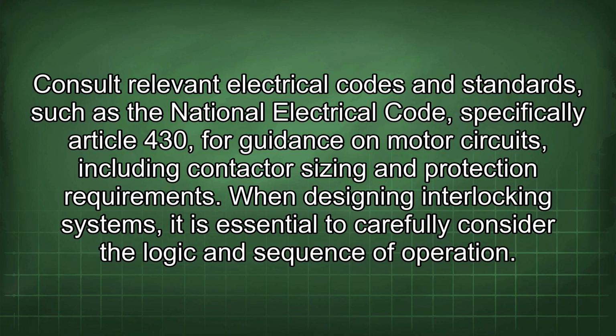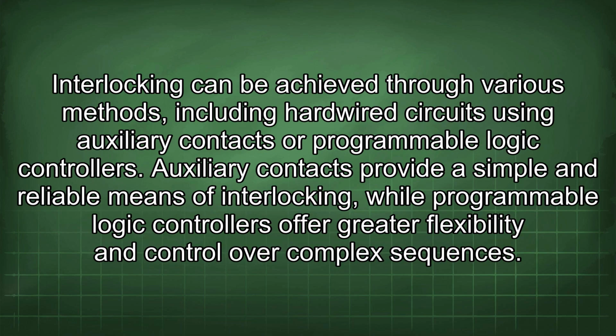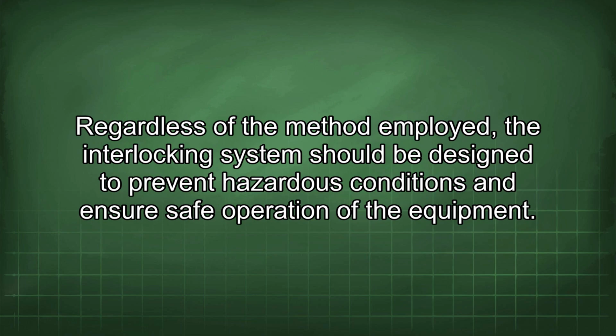When designing interlocking systems, it is essential to carefully consider the logic and sequence of operation. Interlocking can be achieved through various methods, including hardwired circuits using auxiliary contacts or programmable logic controllers. Auxiliary contacts provide a simple and reliable means of interlocking, while programmable logic controllers offer greater flexibility and control over complex sequences.